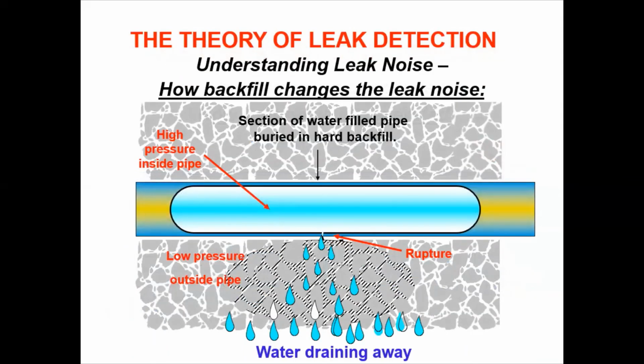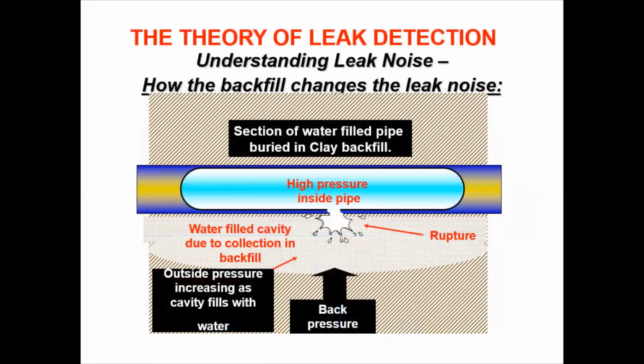Backfill can also create some issues. If you have backfill that's able to let the water infiltrate and drain away, that is a positive thing. That's going to help with the leak sound, meaning it will travel much further on a stretch of pipe, versus if you had some type of clay backfill underneath the pipe that was putting back pressure up against that break. That is not as good for leak sound.